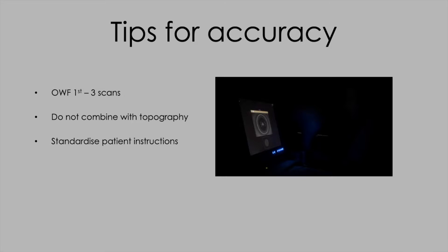Those are the reasons for doing it, and now some tips on acquiring the scans. First, make the wavefront scan the first thing you do in the diagnostic scanning sequence before any of the other scanners or tests, so the tear film is stable and not fatigued by repeated scans — that way you'll get more repeatable measurements.